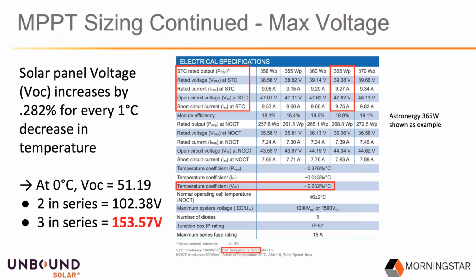What we need to do is account for the effects of temperature on voltage. And that's why I highlighted that temperature coefficient for VOC. What that says is that for every increase of 1 degree Celsius, you lose 0.282% of your volts open circuit. And the opposite happens when it gets cold. If the temperature goes down, your voltage goes up. I think it's kind of intuitive if you think of it as the hotter it is, the less efficient your system works. And then the colder it is, it actually gets more efficient and you can produce a little bit more than the rated value. What we want to do is make sure that this panel is not going to go over voltage and exceed the limits of our charge controller, because that would damage it.